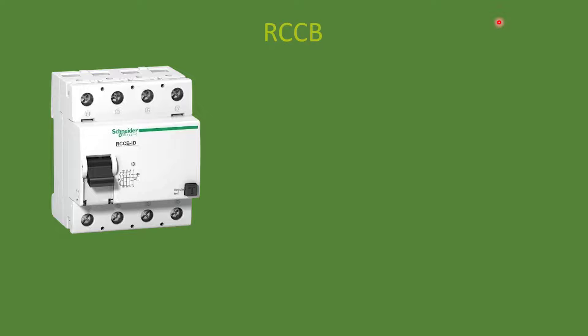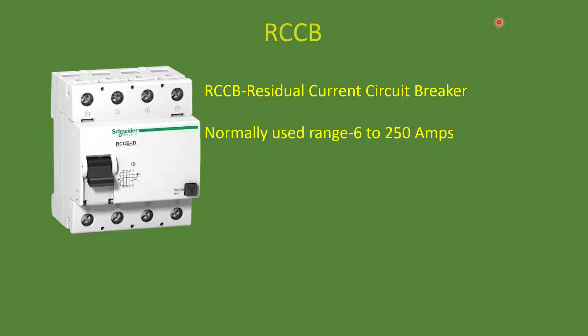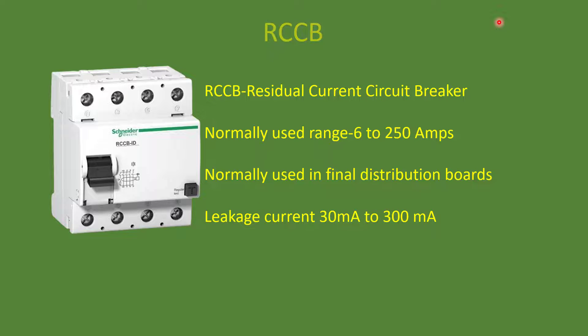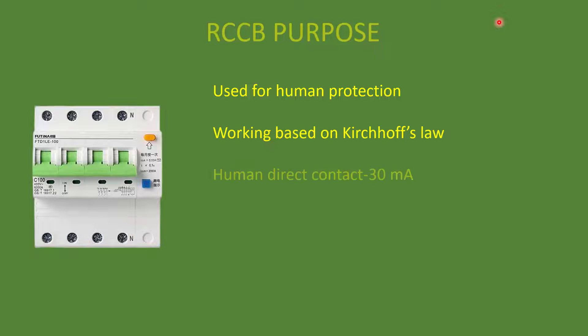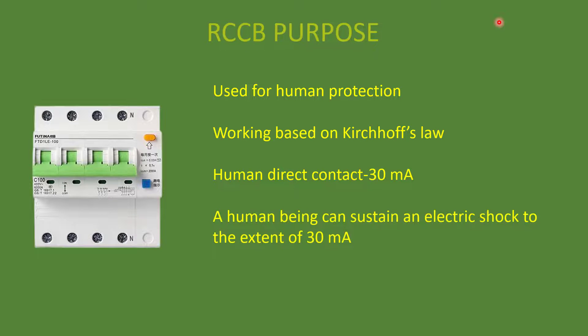Another type of circuit breaker commonly used is RCCB — the full form is Residual Current Circuit Breaker. Normally it is used in the operating current range of 6 to 60 amps. We can find this in the final distribution board inside our home. It can trip from leakage currents starting from 30mA to 300mA. If human direct contact is involved, an RCCB with a 30mA leakage current rating is used. The purpose of RCCB is human protection against electric shocks — a human body can withstand electric shock up to 30mA; above that it can be fatal.